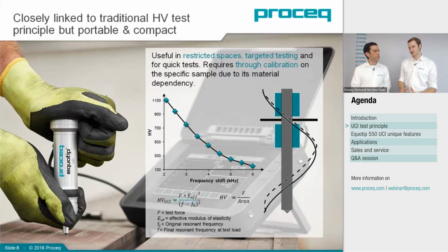In comparison, the formula for stationary Vickers has only the test load and the indentation area, which is usually measured by the diagonals of the indentation. This is really important to keep in mind when we talk about UCI: this test method is dependent on the elastic modulus of the material.